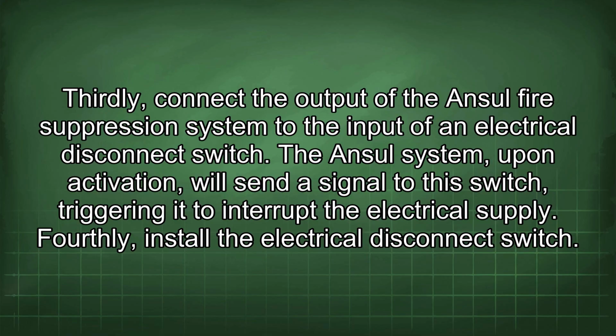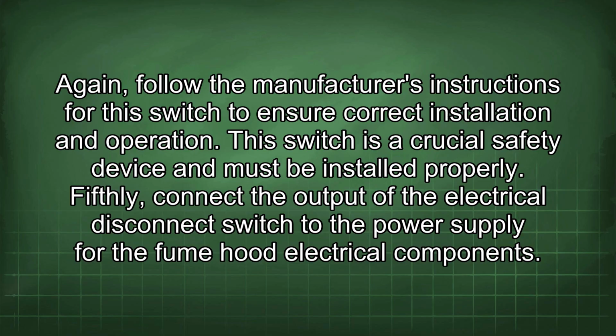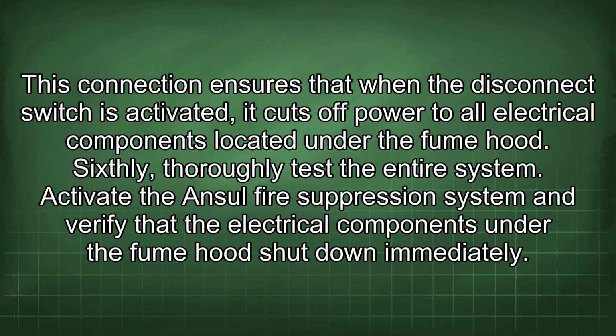Fourthly, install the electrical disconnect switch. Again, follow the manufacturer's instructions for the switch to ensure correct installation and operation. This switch is a crucial safety device and must be installed properly. Fifthly, connect the output of the electrical disconnect switch to the power supply for the fume hood electrical component. This connection ensures that when the disconnect switch is activated, it cuts off power to all electrical components located under the fume hood.